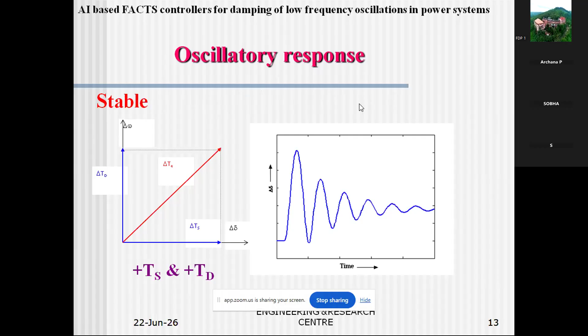So this is what is expected of a system. With respect to rotor angle stability, you have to make sure that there is enough damping torque in the system. That means you are going to examine the oscillatory response of the system, which you call low frequency oscillations. That is, low frequency oscillations in a power system due to lesser damping torque.